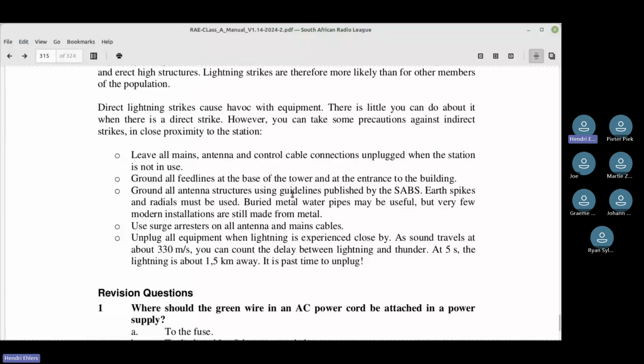All structures, the SABS has got a lot of specifications when it comes to earthing. What a lot of people do is dig out a huge area, put in rebar, the reinforcement squares used when casting concrete floors, place that under the ground, tie everything together to earth spikes, and then put the concrete on top, in order to get a huge area that is grounded.